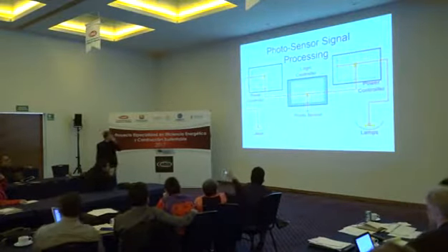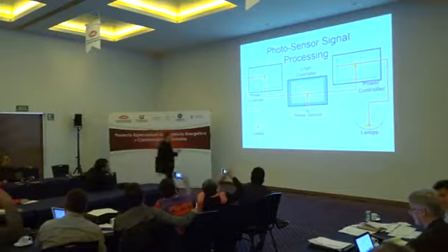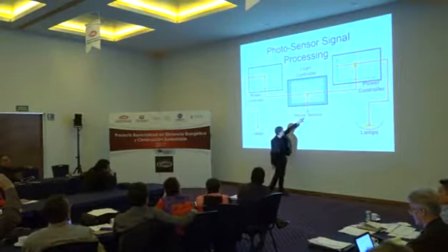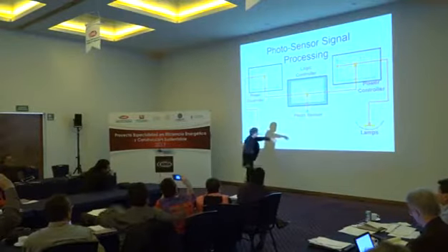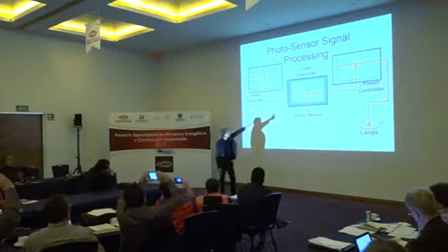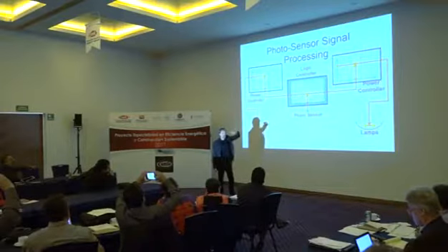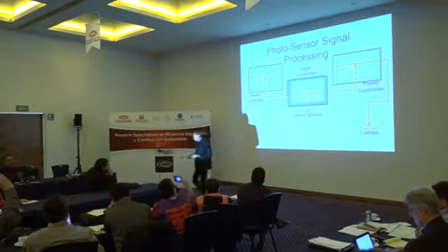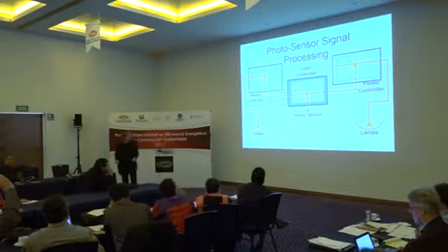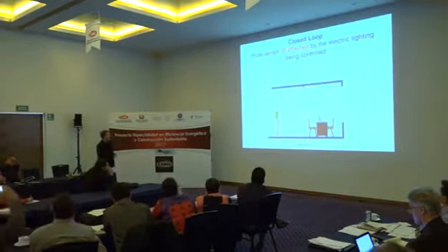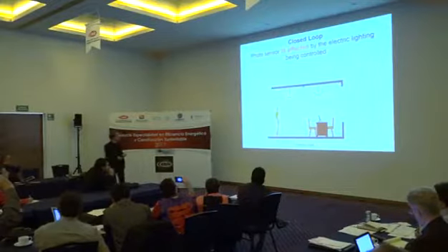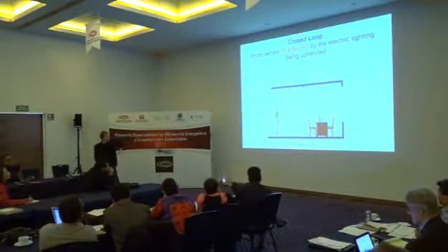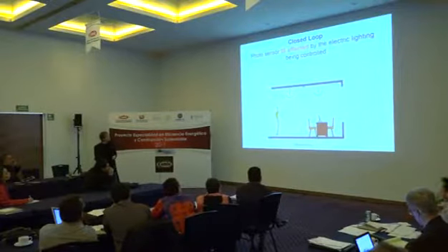Okay. So the basic process for both approaches is that the photosensor sees light. There's some kind of predetermined logic that says, do this. And then the power controller chokes back or turns back the electric lighting. So I'm going to go through this in process. Closed loop: the sensor's on the ceiling. It's looking inside the space.